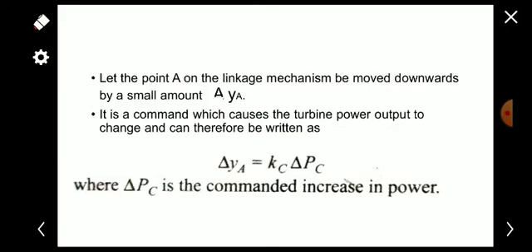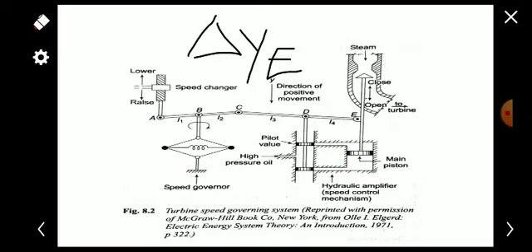The command signal delta_pc sets into motion a sequence of events: the pilot valve moves upwards, high pressure oil flows onto the top of the main piston moving it downwards. When the pilot valve moves upwards, point D moves upwards, high pressure oil comes to the piston through this path, the piston moves downwards, the steam valve opens, and consequently the turbine-generator speed and frequency increase.